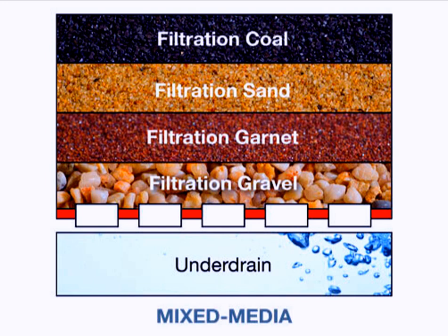Anthracite. Crushed and graded anthracite is often used as a filter medium along with sand. It is much lighter than sand, so it always stays on top of the sand during backwashing. It is usually graded to a size slightly larger than sand.